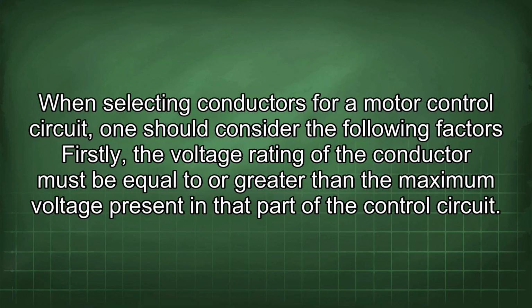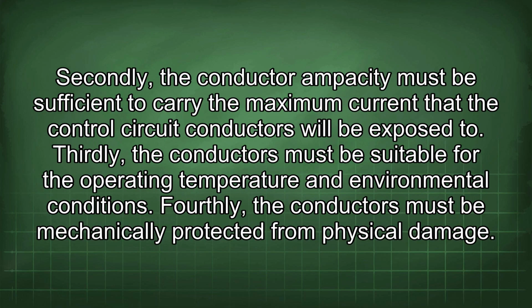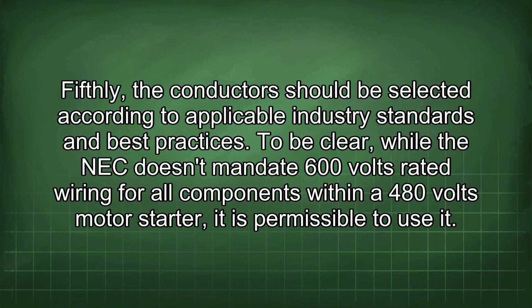When selecting conductors for a motor control circuit, one should consider the following factors. Firstly, the voltage rating of the conductor must be equal to or greater than the maximum voltage present in that part of the control circuit. Secondly, the conductor ampacity must be sufficient to carry the maximum current that the control circuit conductors will be exposed to. Thirdly, the conductors must be suitable for the operating temperature and environmental conditions. Fourthly, the conductors must be mechanically protected from physical damage. Fifthly, the conductors should be selected according to applicable industry standards and best practices.